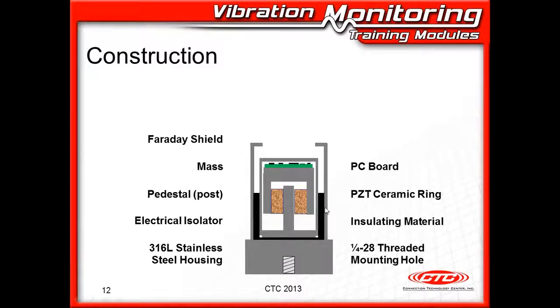And then we're going to fill the inside with epoxy. What we want to do is keep everything centered, and keep everything electrically isolated. So all this black area now becomes our electrical isolation from any ground loops. So this sensing element is totally isolated inside the sensor case. We're going to put on our hermetic connector. It could be a 2-pin or 3-pin or 4-pin even, depending on the type of sensor we're using.